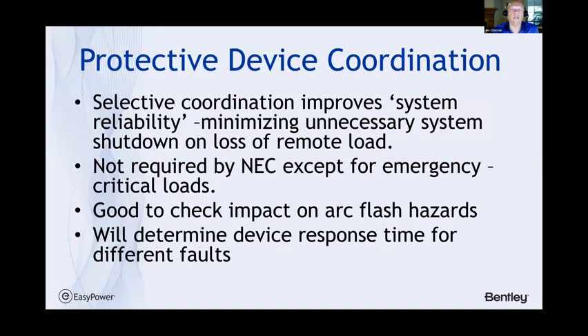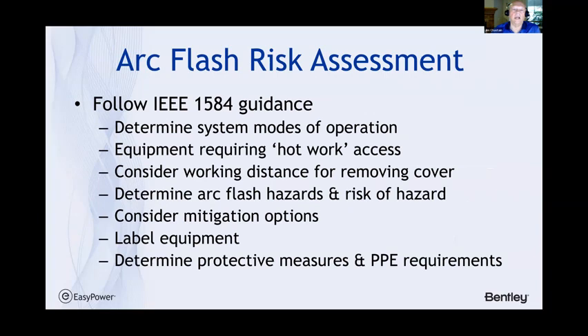And then protective device coordination is usually included in this step, and involves a selective coordination to improve system reliability, which means you minimize the unnecessary system shutdown on loss of remote load. It's not required by the National Electrical Code except for emergency critical loads, but it's good to check to make sure what the impact is on arc flash hazards, and it will determine which response time needs to be adjusted for mitigating arc flash. And then based upon that, following the IEEE 1584 guidance, you can complete an arc flash assessment. Again, it's a heavy calculation intensive step, and most of the software will handle it, but it requires knowledge of how to apply the software conditions.